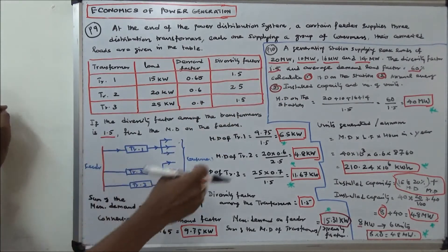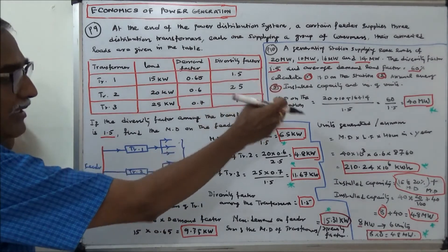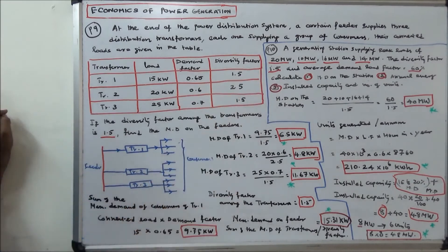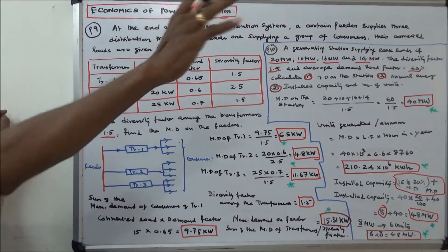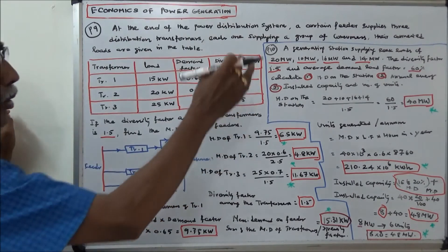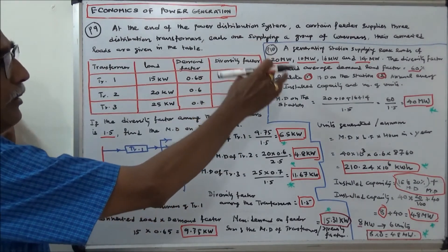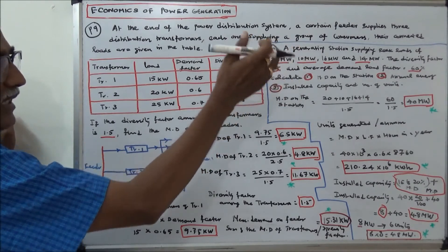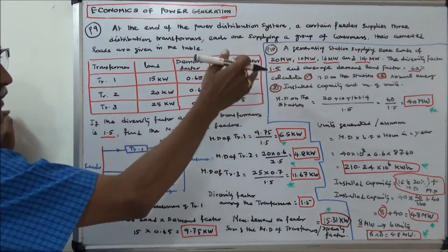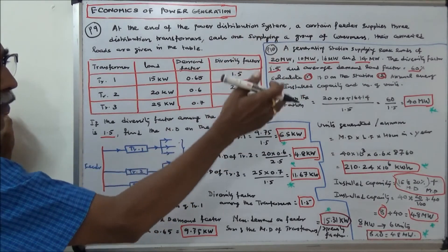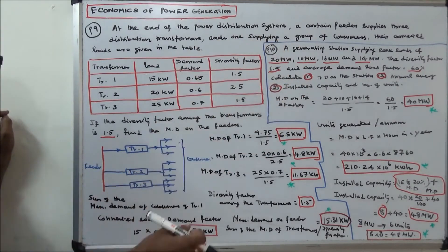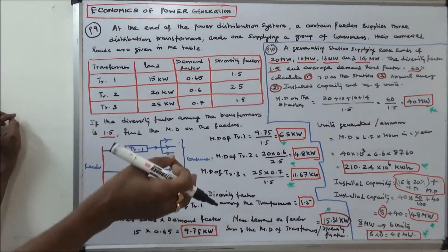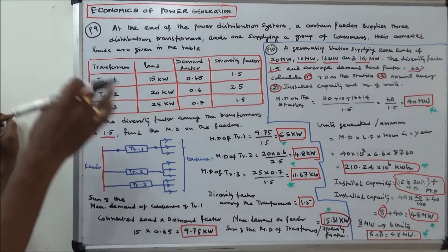First, we calculate the maximum demand on the station. That equals the sum of the peak loads — 20 plus 10 plus 16 plus 14 equals 60 — divided by the diversity factor 1.5, giving 40 megawatts. That is the maximum demand on the station.